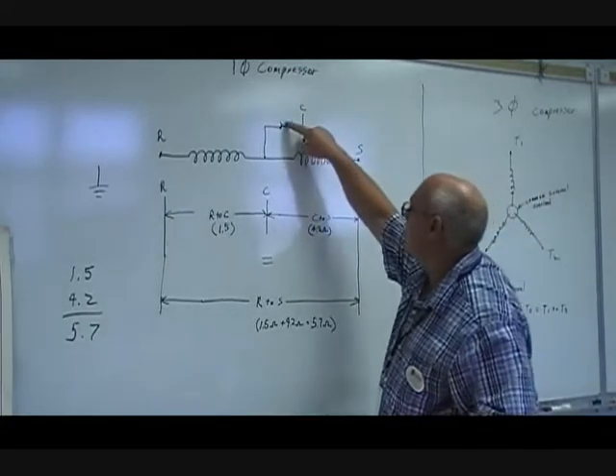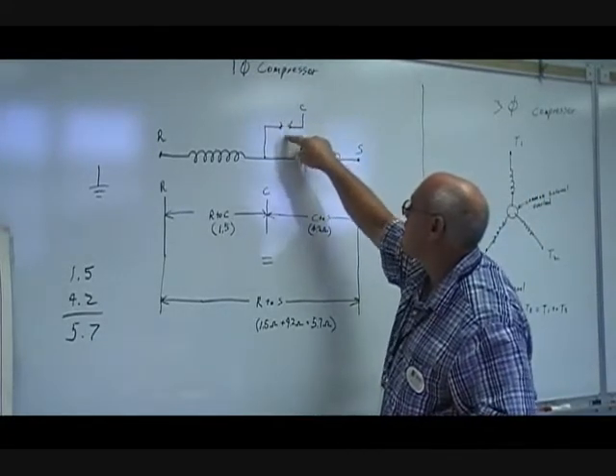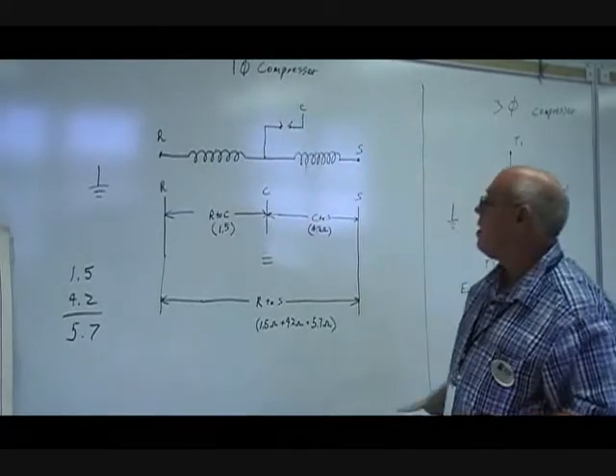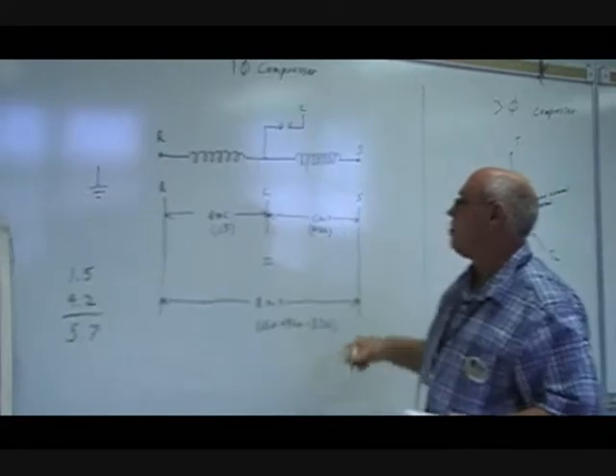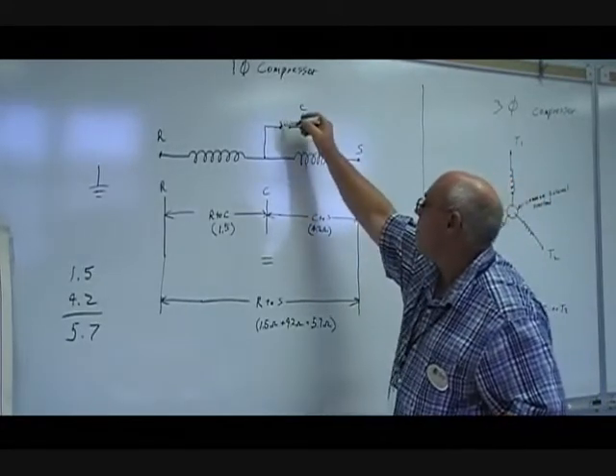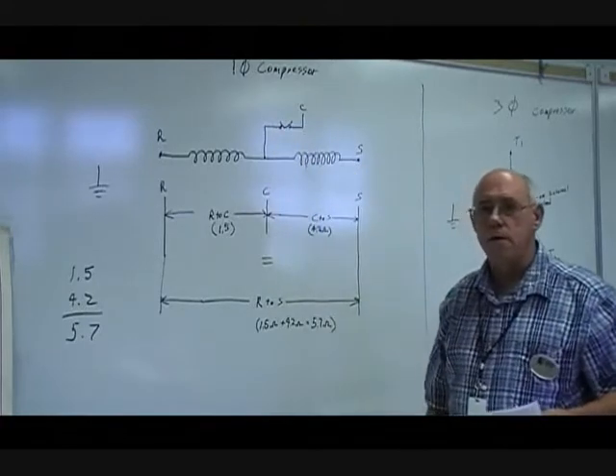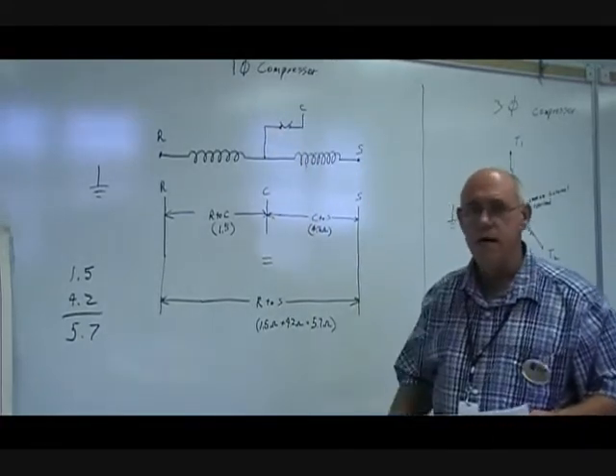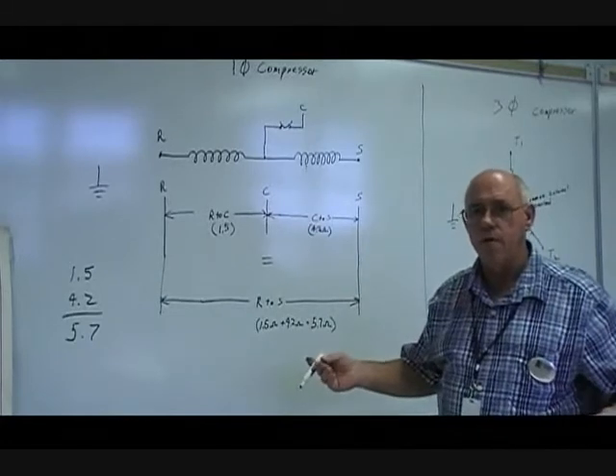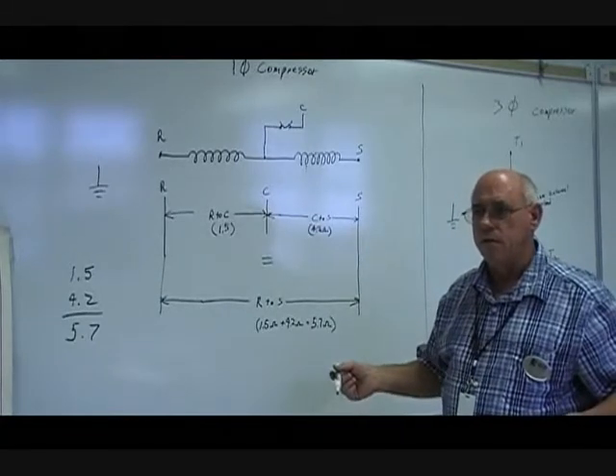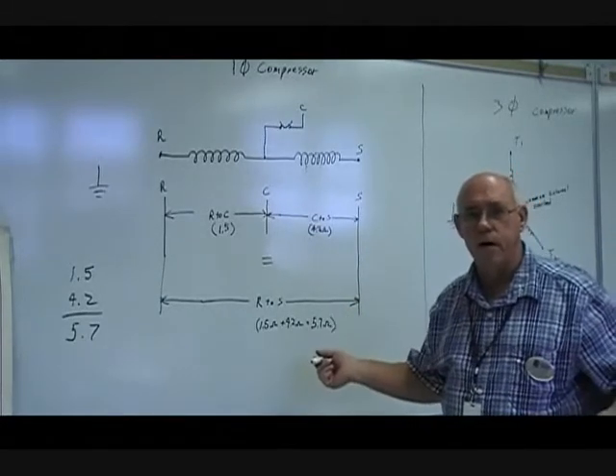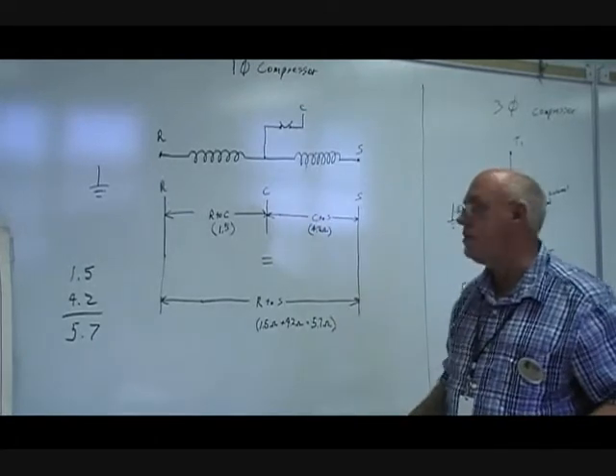One of the ones that's really misdiagnosed many times is an open overload. People will think that's a bad compressor. You have to give this overload time to reset. If the compressor is warm and has tripped that overload, it may take as much as eight hours to reset. So do not condemn a compressor until you've given it time to reset.